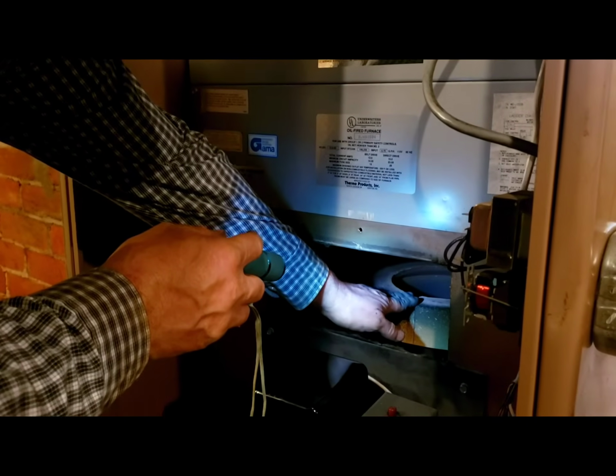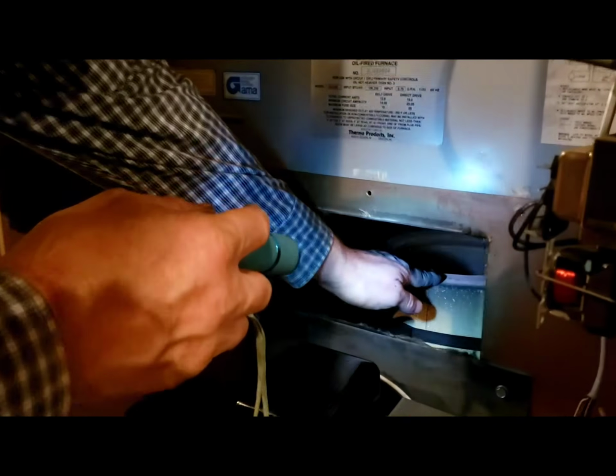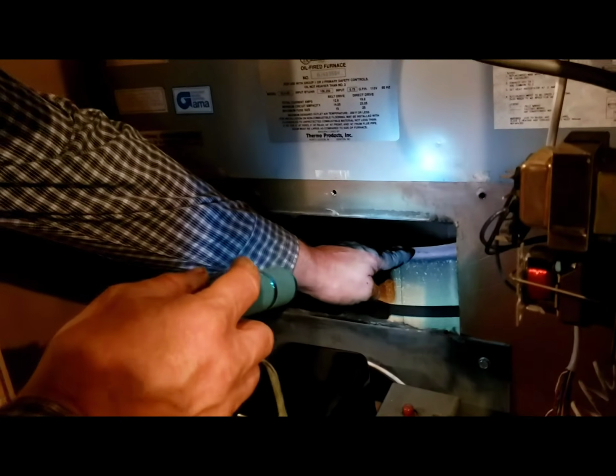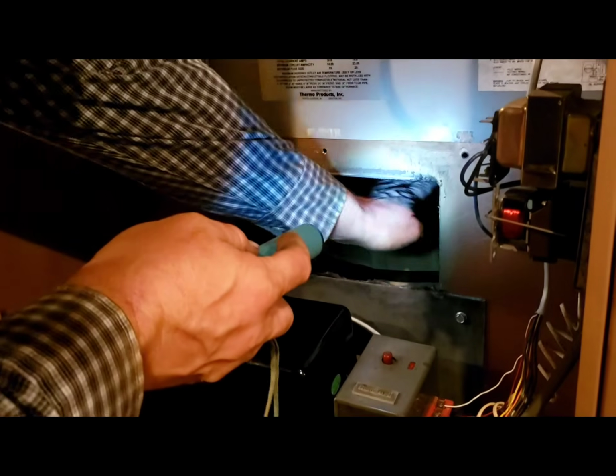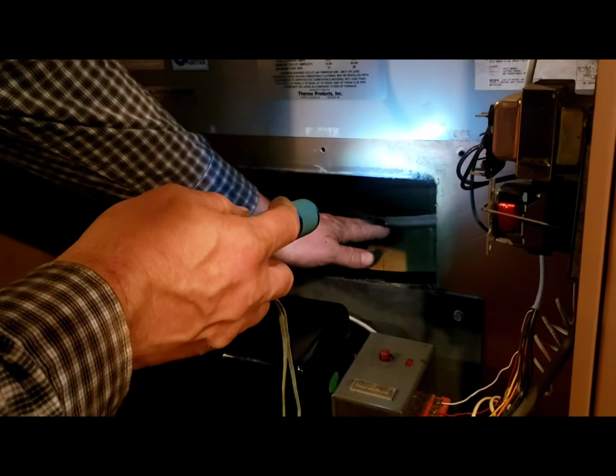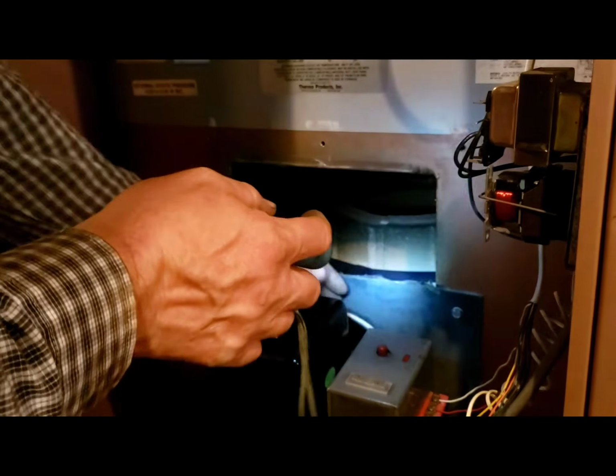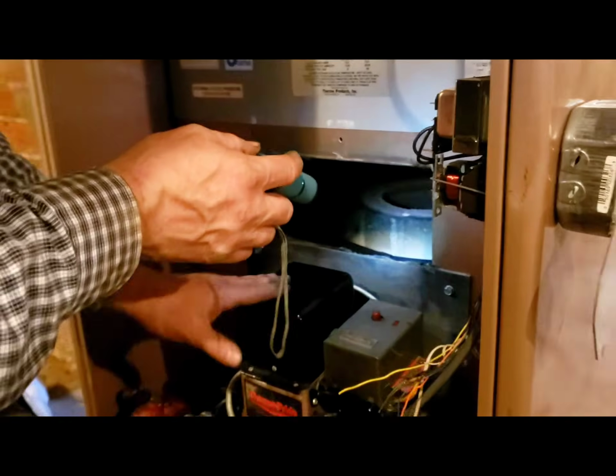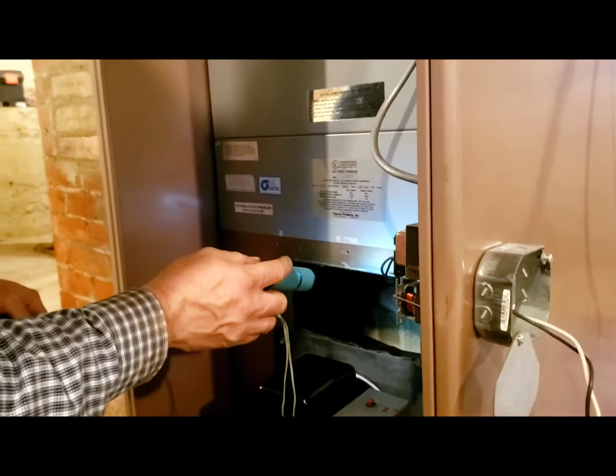Basically what you do is put it up to the top of your combustion chamber, which sits inside your heat exchanger. It says in the book, don't put it around the back of the combustion chamber, just up in this cavity, and that keeps your transformer, your primary control, your gun tube, everything cool.